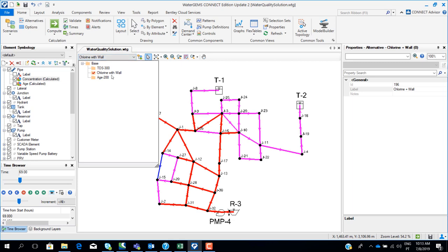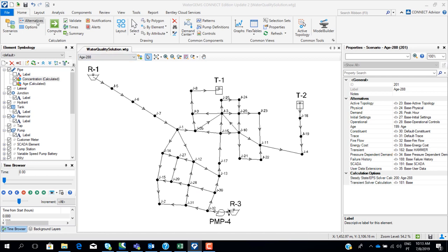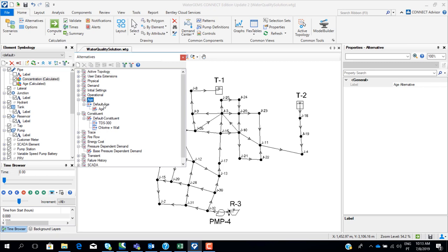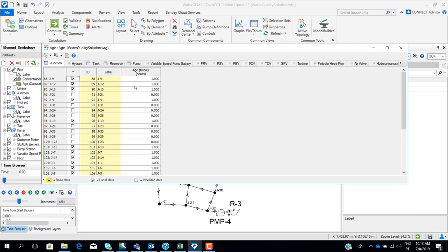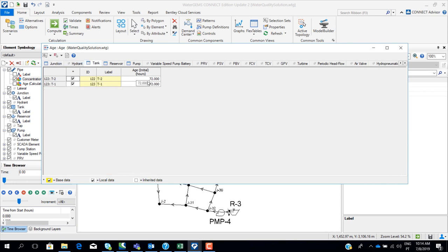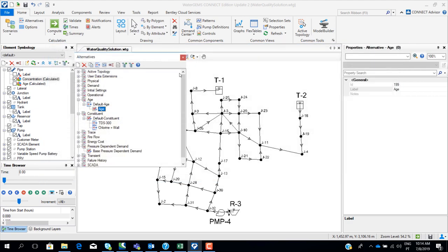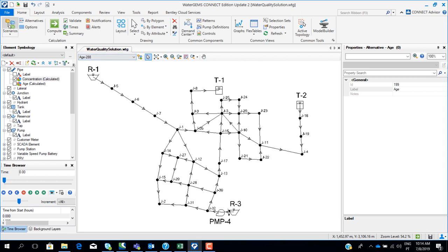Now let's model the age of the water inside the network. The difference here is that we have to input the initial age of water for time step zero in the age alternative. At some nodes we have an initial water age of one hour. At the tank, we are assuming the water was there for 72 hours, and reservoirs are set to zero hours.